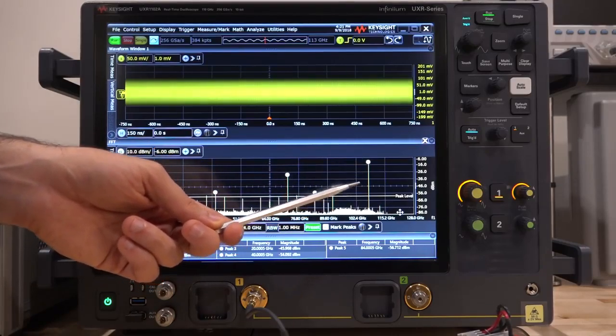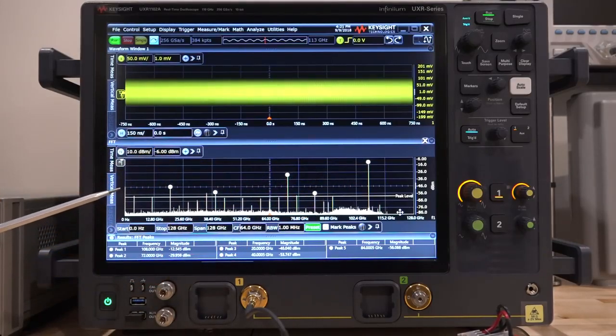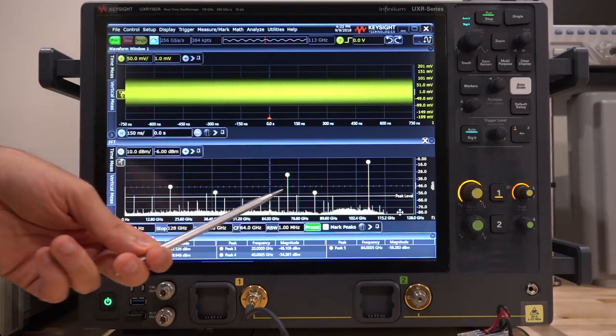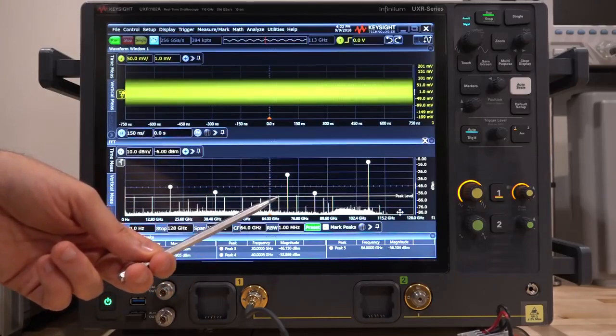And the fundamental signal sitting all the way out there is, of course, now significantly larger. And you can see a whole bunch of other harmonics here. These are all the multiples of 18, as well as all the other harmonics that this old synthesizer is producing. They're all mixing. Intermodulation products are showing up. They're just all over the place. Now, to do a meticulous test to figure out which of these is coming from what, and if any of them are coming from the A2D converters of the oscilloscope, a much better source is required, and I'm going to save that for when we get the final version of the instrument. But nonetheless, we can clearly see that this instrument is going to have a very strong 4th harmonic coming out.